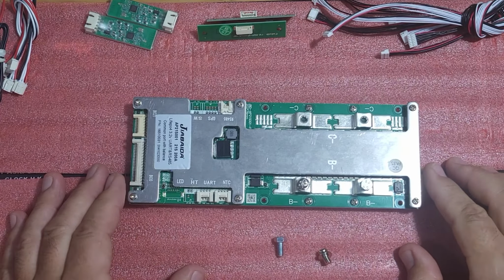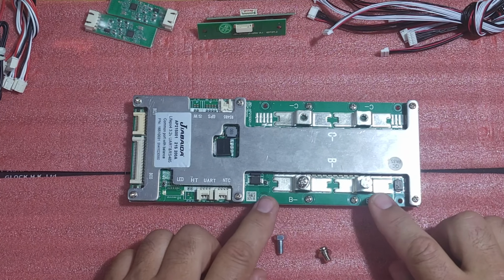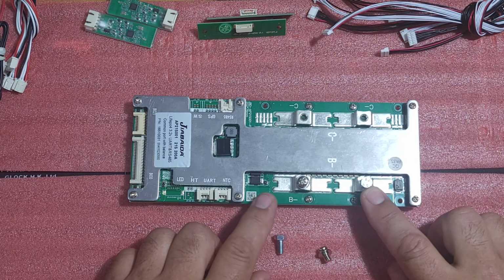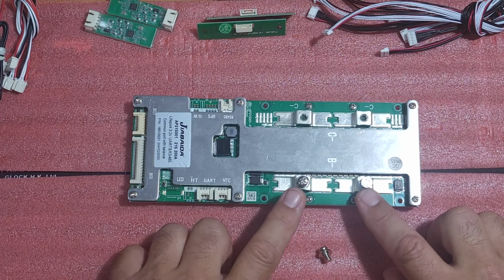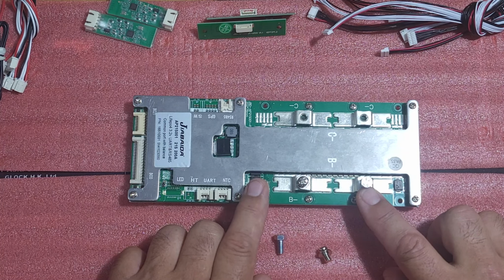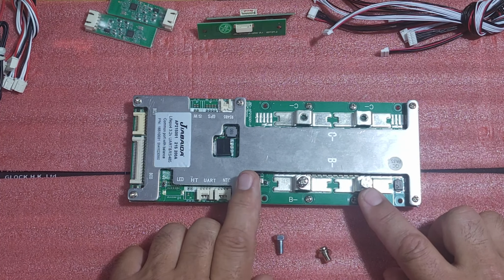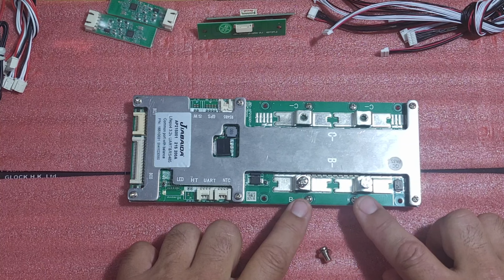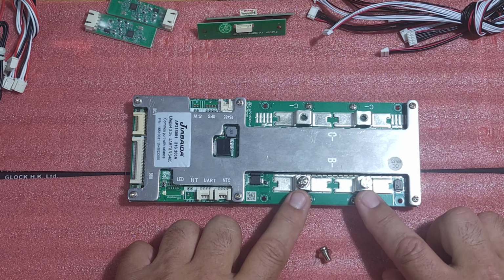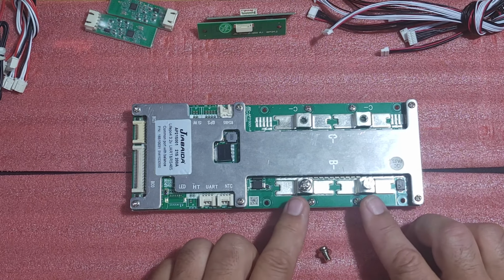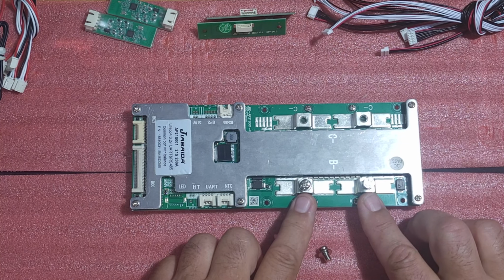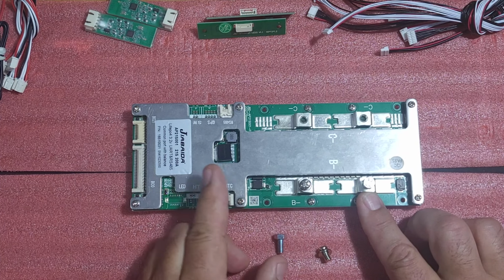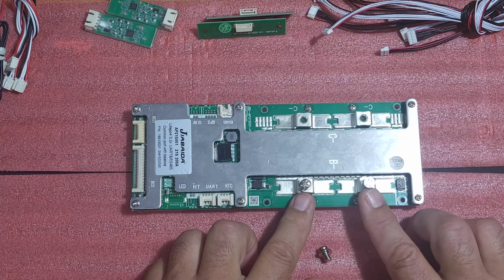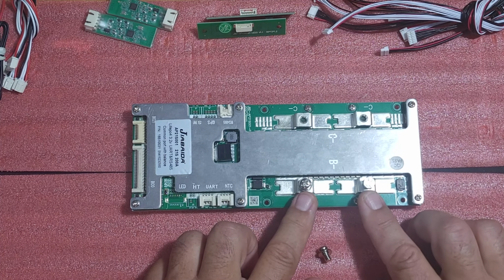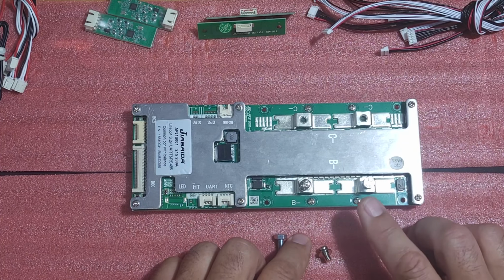All right, with a lot of BMSs, you will see multiple lugs on the BMS. Now, some of the older versions are single lugs in, single lugs out. The model prior to this had 3 lugs in and out, and you'll see some with 4. This newer auto sensing version only has 2 lugs. Now, with these multiple lug units, the current carrying capacity is split between the various lugs. And this is a 200 amp BMS, and they're splitting the current carrying potential between 2 lugs, so that could be 100 amps and 100 amps in each lug.